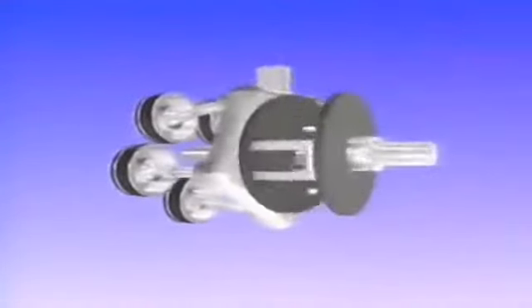The DCW17BE variable displacement compressor is a 5-cylinder wobble plate compressor. The angle of the wobble plate determines the stroke of the pistons. Longer strokes equal greater capacity. Shorter strokes equal less capacity. Displacement can be varied from full 100% capacity to a minimum displacement of 5%.